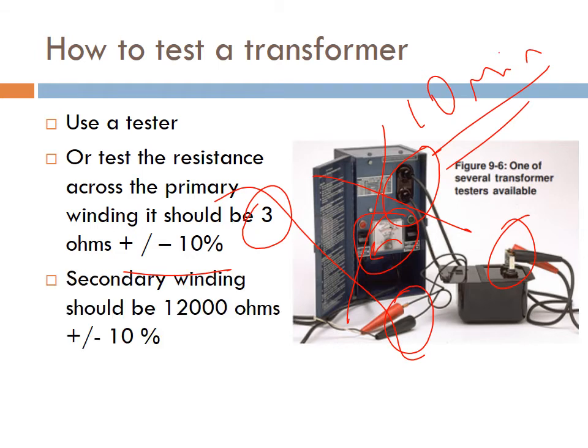Then you can test the secondary. This is your secondary here, so you can test for resistance, meaning that there's no voltage coming into your transformer, and you should be around 12 kilo ohm, so 12,000 ohms, again plus or minus 10%. That should indicate a good transformer. These are two ways to test a transformer.